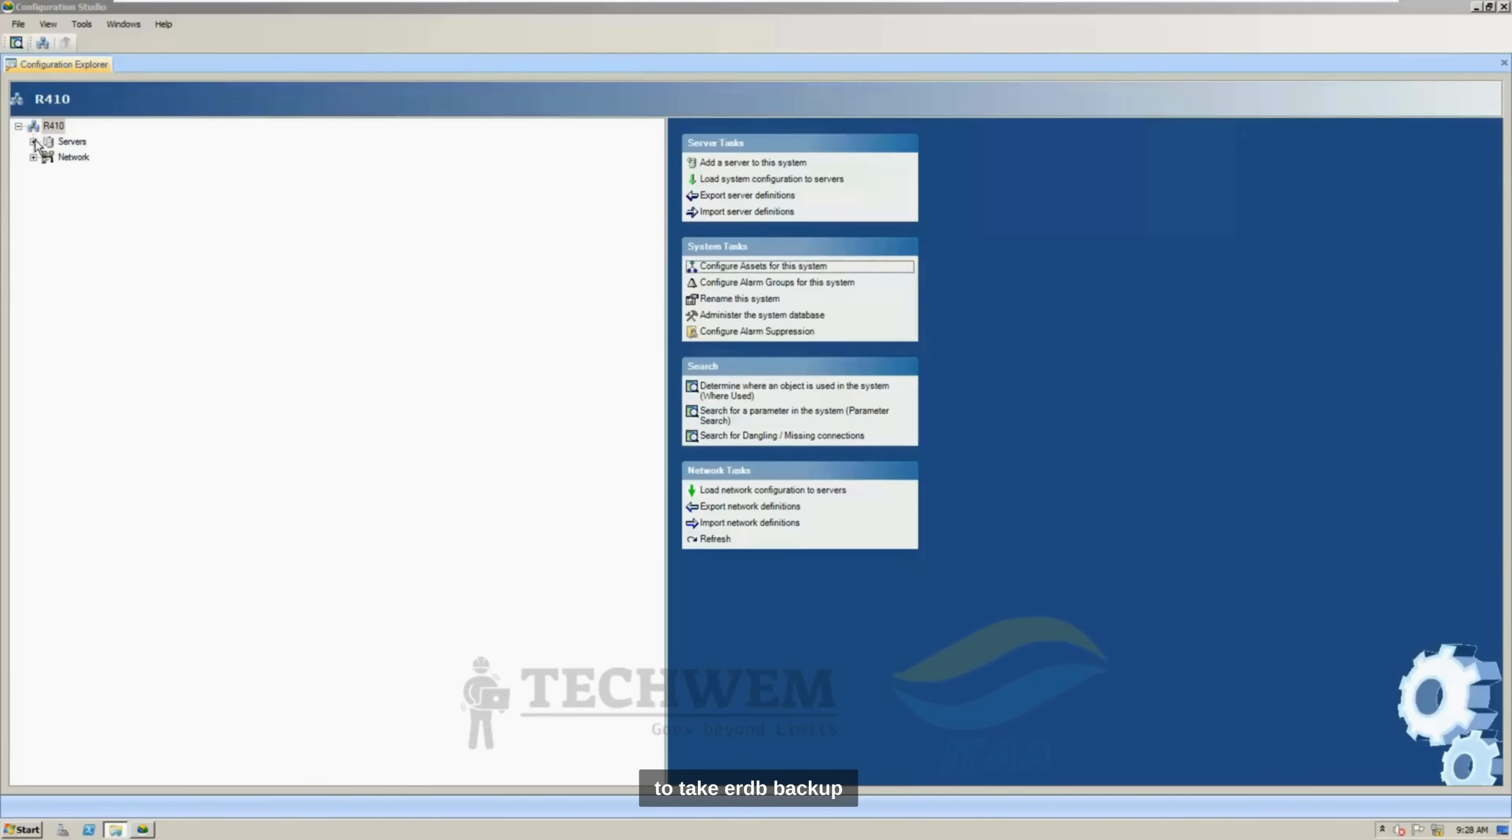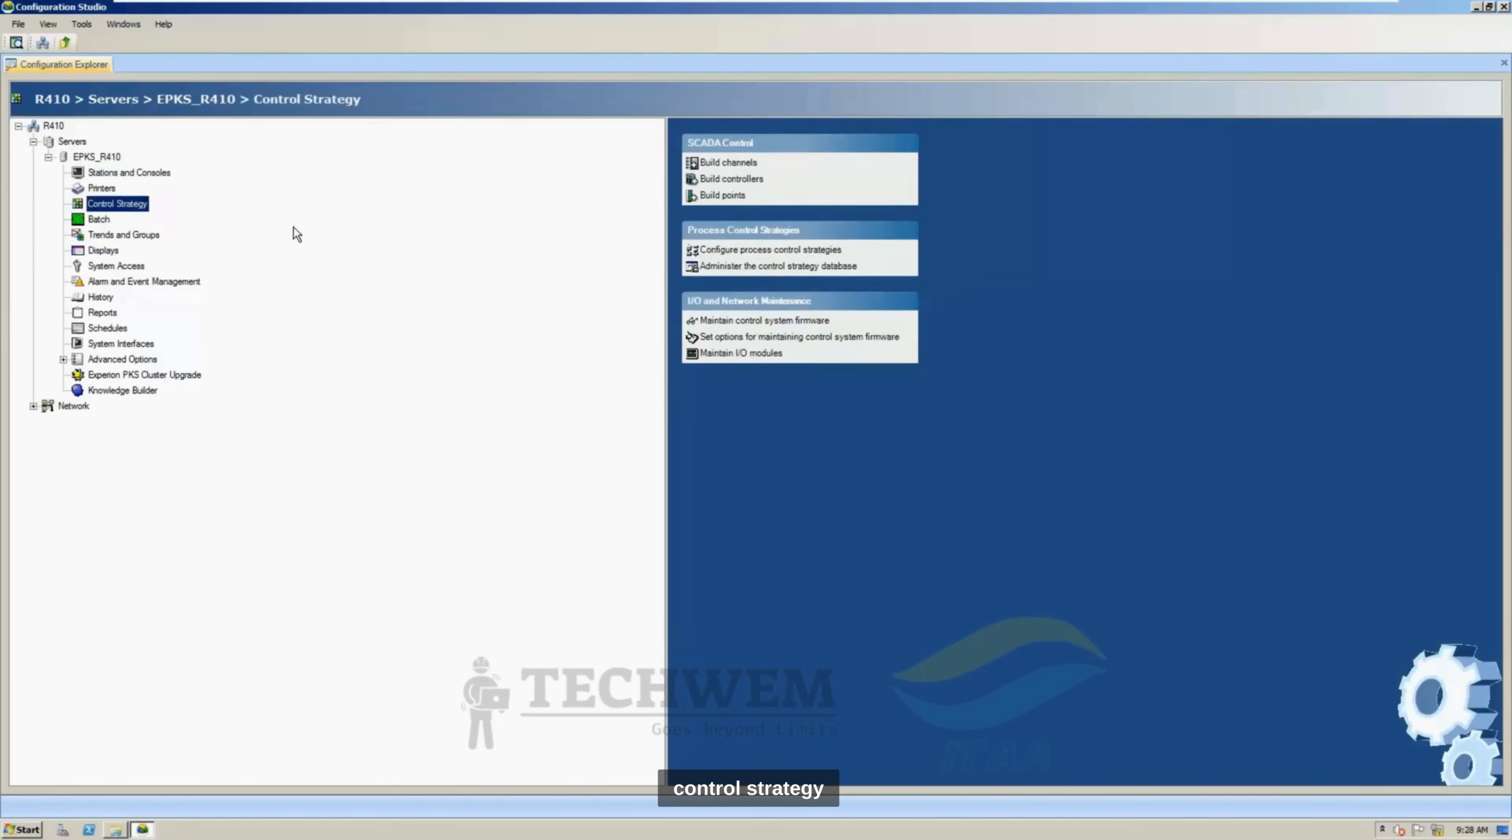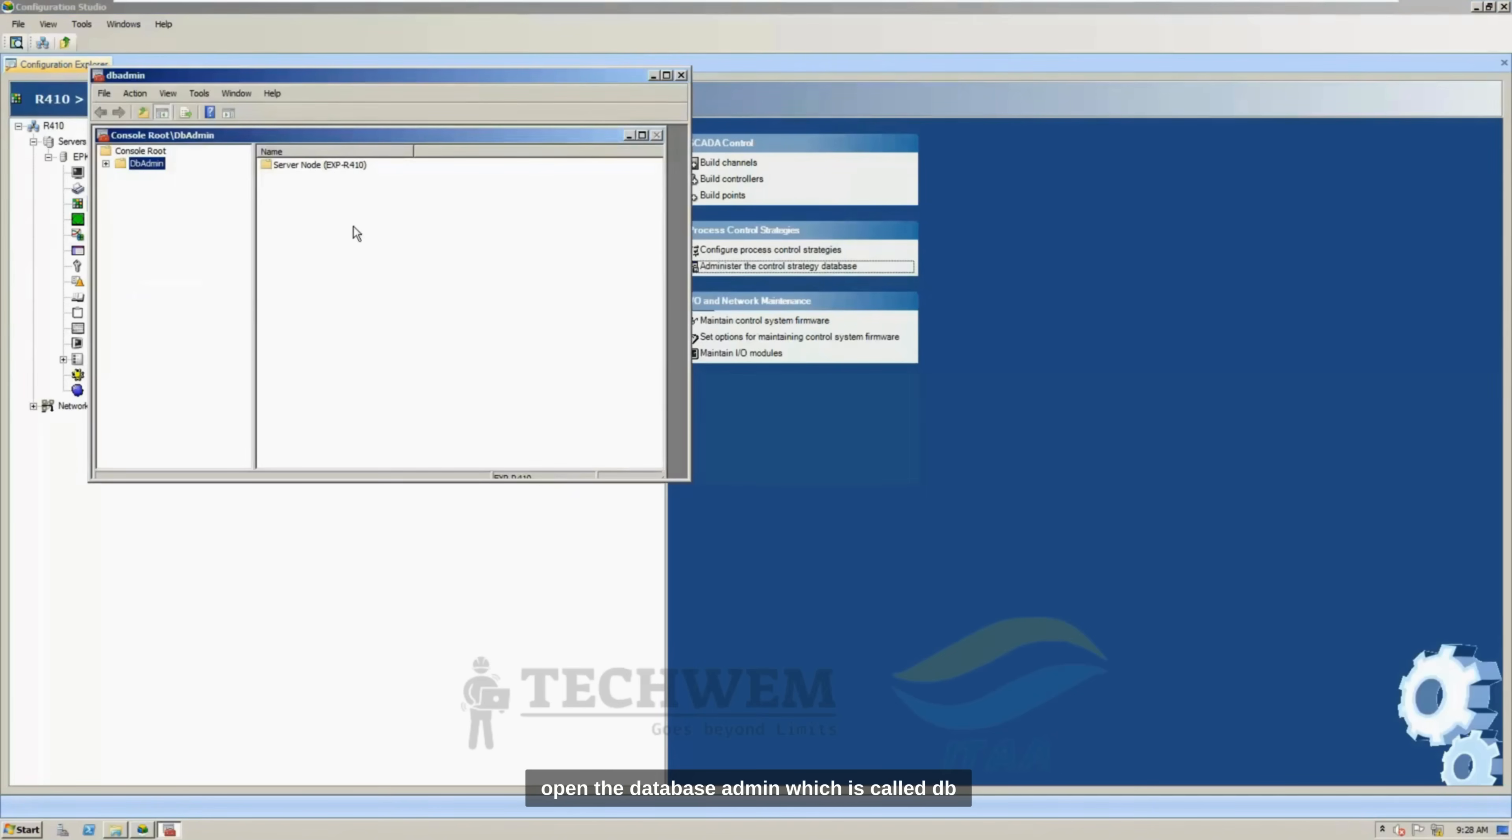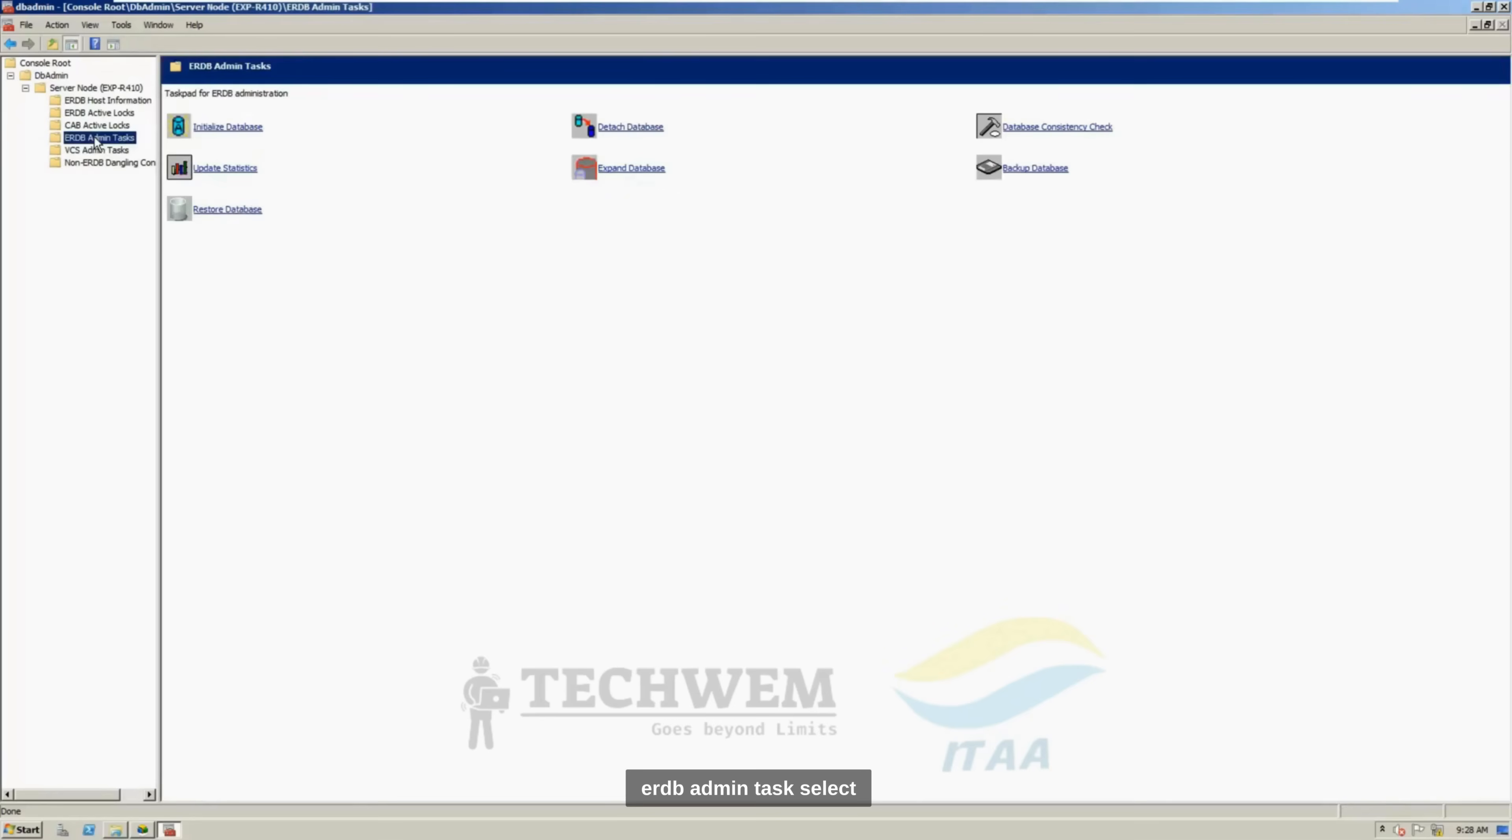To take ERDB backup, we have to go to server, click on control strategy, click on administrate the control strategy database. And it will open the database admin, which is called DB admin. Expand all the windows, click on DB admin, click on ERDB admin task.